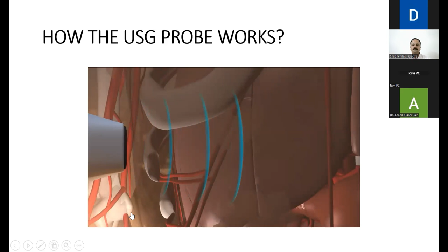So the whole idea of showing this video is that AC current is applied to the probe. There are piezoelectric crystals in the probe. The piezoelectric crystals generate ultrasound waves. The ultrasound waves go into the tissues. They strike the structures in the tissue. Then they reflect back, refract back, and some of them get attenuated in the tissue. So those ultrasound signals that come back to the piezoelectric crystal on the probe are then converted into the images on the screen. So that is how our probe works.